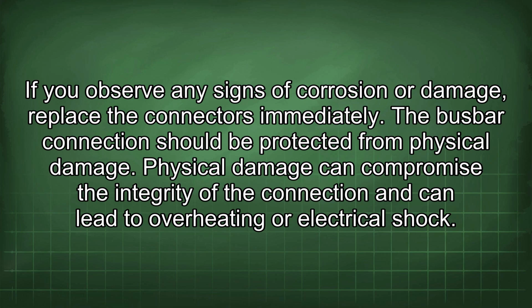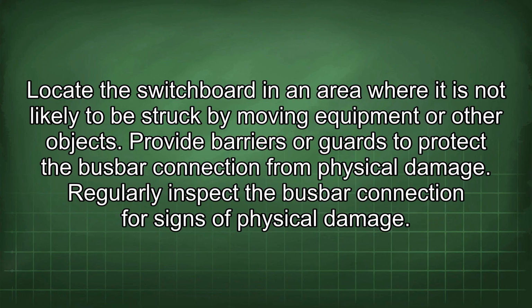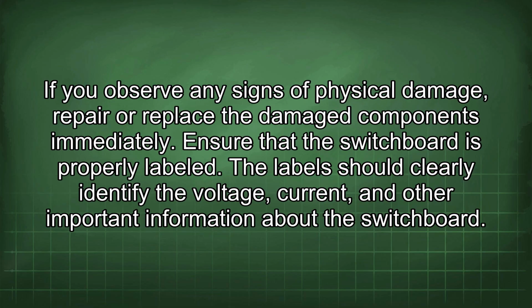The busbar connection should be protected from physical damage. Physical damage can compromise the integrity of the connection and can lead to overheating or electrical shock. Locate the switchboard in an area where it is not likely to be struck by moving equipment or other objects. Provide barriers or guards to protect the busbar connection from physical damage. Regularly inspect the busbar connection for signs of physical damage. If you observe any signs of physical damage, repair or replace the damaged components immediately.